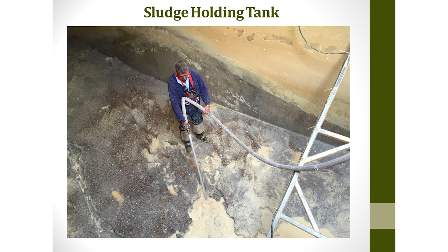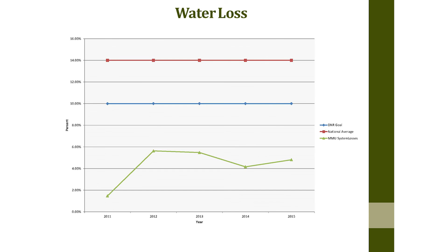With our KPIs, our key performance indicators, like Steve mentioned a few on the electric side, there's water losses. Water loss in the state of Minnesota, the DNR likes it to be under 10%. That's the blue line on this graph. National average is 14%, the red line. In Marshall, we're the green line, usually around 4 or 5%. That's due to our maintenance programs, fixing leaks in a timely manner, and keeping our water meters accurate.